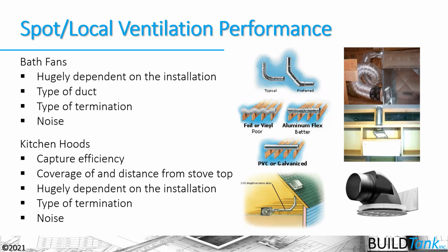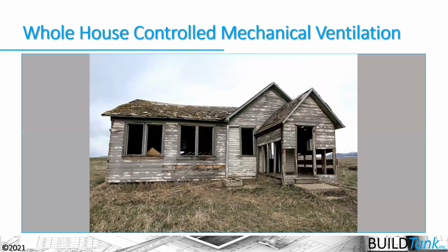And just the biggest hint here is that we need roughly a 1 to 2 foot straight duct run out of the fan before we put any elbow in that duct, because you basically have to build velocity of that air and reduce turbulence in that air as it's leaving the fan housing, before it can actually get all the way outside through elbows in that ductwork. But obviously we don't want to tie the duct into a knot like we see in the upper right-hand picture. These installs really impact the ability of that fan and local exhaust ventilation to work here. So let's move into whole house controlled mechanical ventilation systems here.